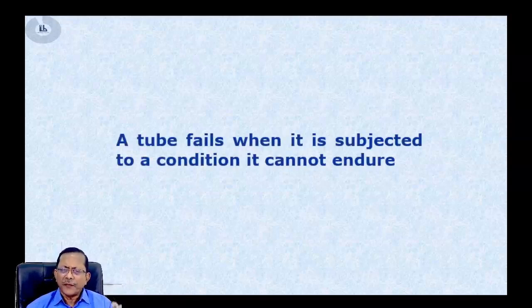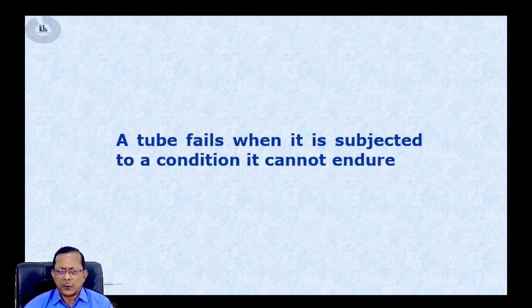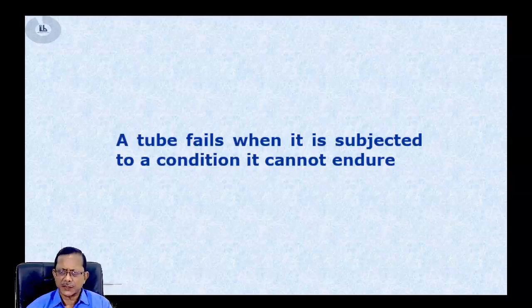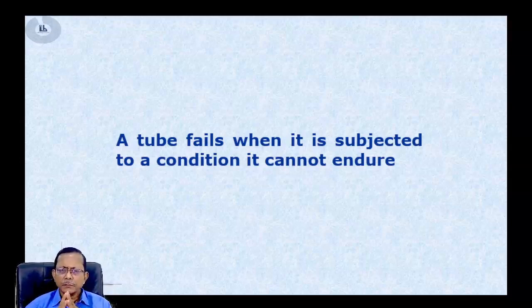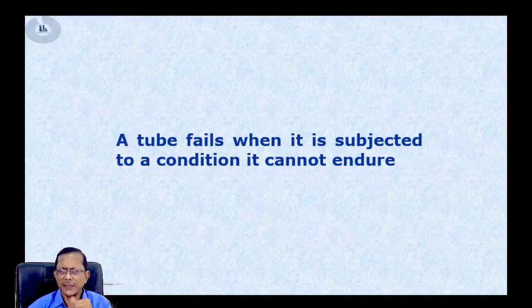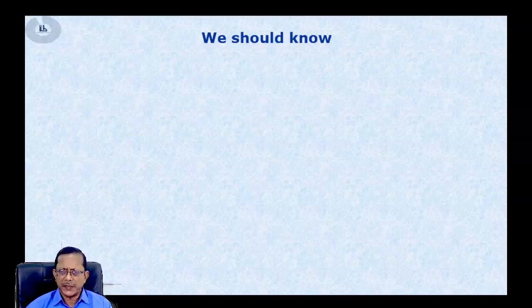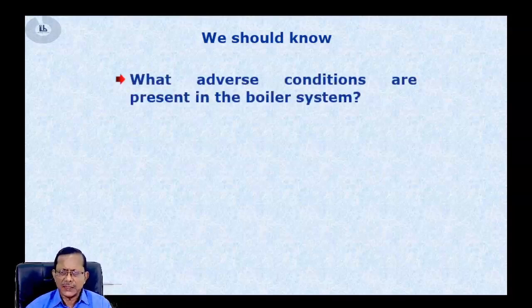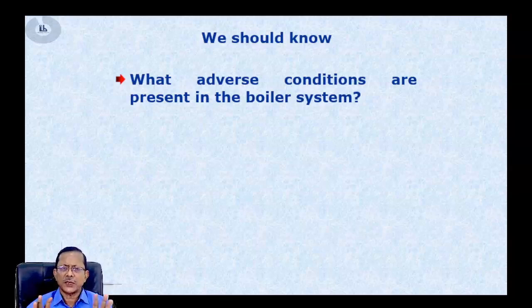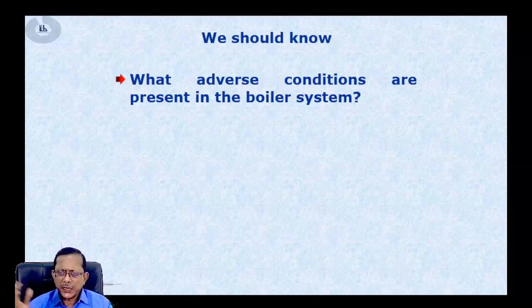Simply speaking, a boiler tube fails because it is working under a condition it cannot endure — its strength is not enough for the condition under which it is working. That condition was created by us: by a designer, during erection, during operation, or even during maintenance. To prevent tube failure, we should know what adverse conditions the boiler system works under and which adverse condition leads to which kind of damage mechanism.